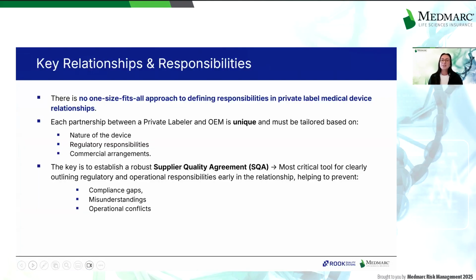There is no one-size-fits-all approach to defining responsibilities in private label medical devices. Each partnership between the private labeler and the OEM is unique and must be tailored based on the nature of the device, regulatory responsibilities, and commercial arrangements. The key is to establish a robust supplier quality agreement, or SQA, as it is the most critical tool to clearly outline regulatory and operational responsibilities early in the relationship, helping to prevent compliance gaps, misunderstandings, and operational conflicts.